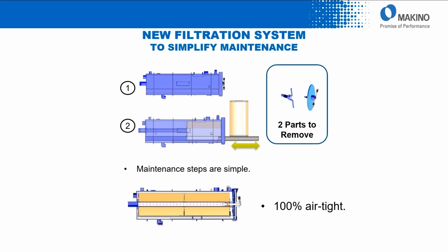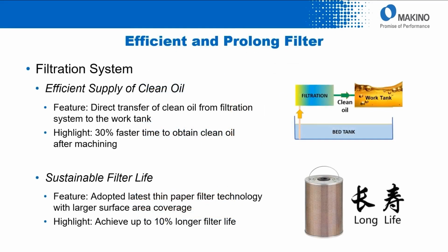So we have the canister itself, the paper filter that's inside, and just 2 parts to remove to get to that paper filter. So there's the lid and then the nut itself that holds the filter in. And with this canister system, 100% airtight system, so less chance for leaks. So the filtration system is really an efficient supply of clean oil.